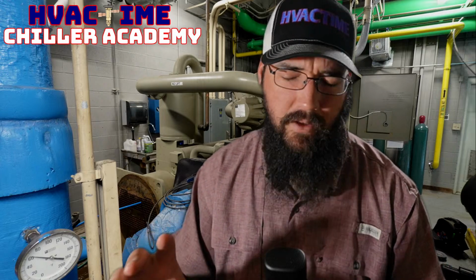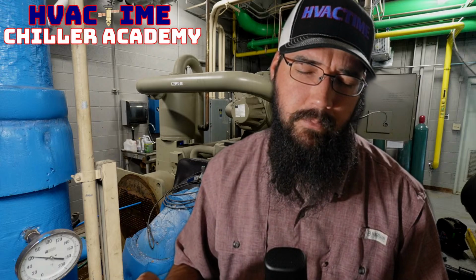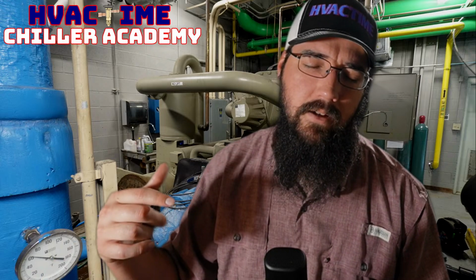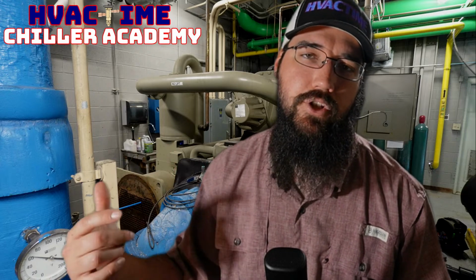Now, you can get to a situation where the flow is so low that you start pushing the low suction pressure points, right? But you'll typically have a very low approach with low flow. Recently I've gone back through some of my much older streams, and I see that as I have learned and grown as a tech, I've had to change how I explain things quite a lot. I don't know that I explained it then the way I would now. And so, yes, with low flow, you're going to have a lower approach just because of contact time.